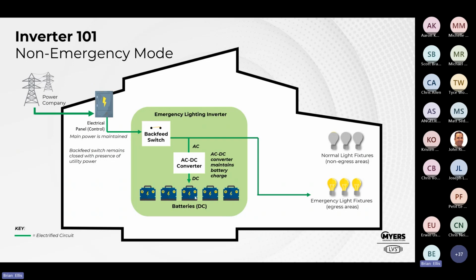It's also trickle charging the batteries, right? So this AC DC converter is allowing DC to go this way. And then when utility goes away, it's going to go the other way and it's going to convert DC to AC. So this actually meets NFPA 101 because our lights are on all the time, right? That's a night light or unswitched. But then we also need to switch our normal lights. So what we're going to do is we're going to pop in a J-box and we're going to put in some kind of lighting control device. It doesn't matter if it's a switch, a power pack, a relay, a room controller, whatever it is.